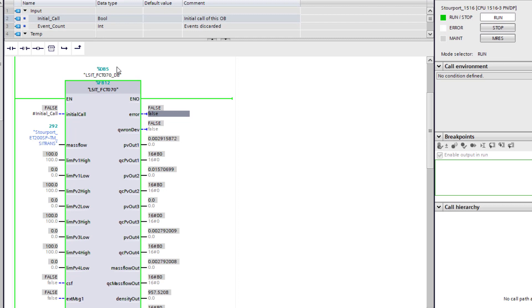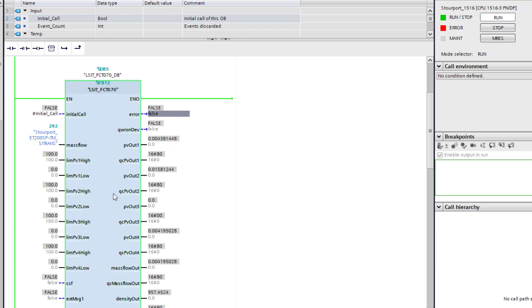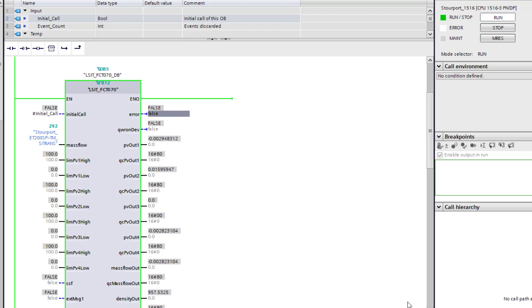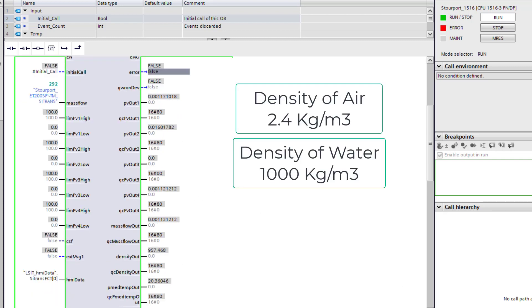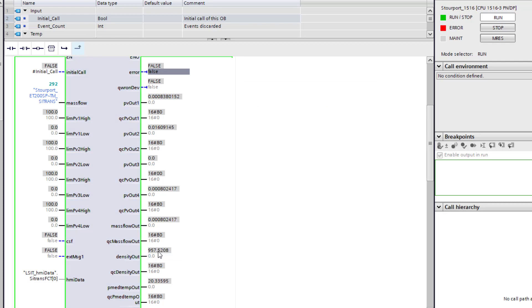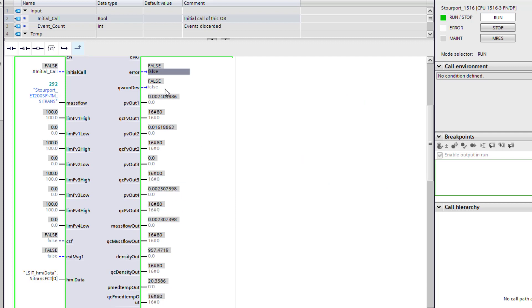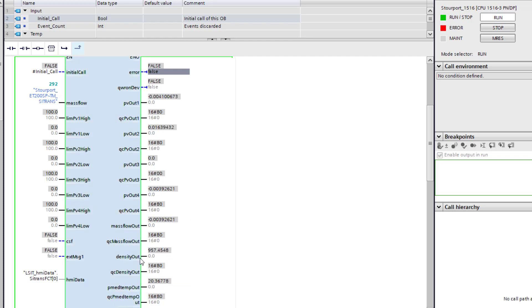Once you have done a compile and a download to the device, just to make sure it is working, just go online. And there are two things to check for. First of all, that you have got data coming in. And there are a few here that makes sense to look at. For instance you can see there my density. And my process media temperature. It will be rare to have one of these working and the others not. So look for things like that. Don't pay too much attention to the flow and the total values. Pick ones that you understand.